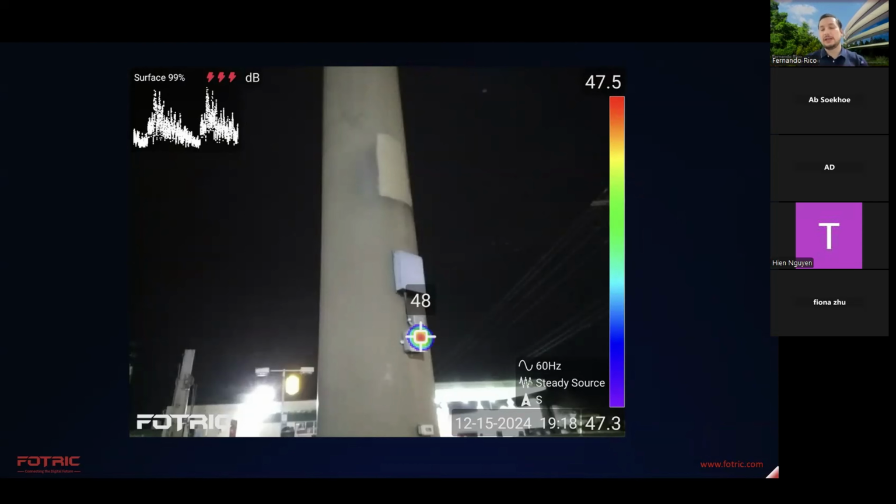This was a food sign like those that you see on the road when you're traveling, with, I don't know, Texaco or McDonald's, those big light signs. We were just passing by, grabbed some food, and then decided to take a look. And effectively, there was tracking or surface discharge coming from that box.